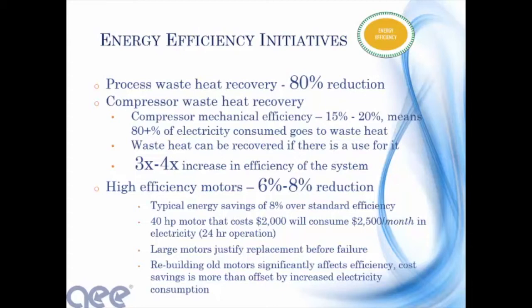High efficiency motors. If you have some older motors in your plants that were standard efficiency and you haven't replaced them yet, the newer motors out there could be as much as 8% more efficient. If you look at a motor that runs around the clock, a 40 horsepower motor, for example, uses $2,500 a month worth of electricity. So that's $30,000 a year. If you can save 6 to 8% of that, you can save a couple $1,000. And that whole motor only costs about $2,000 for a 40 horsepower motor. So on a highly utilized motor, you can almost justify replacing it before it even fails.